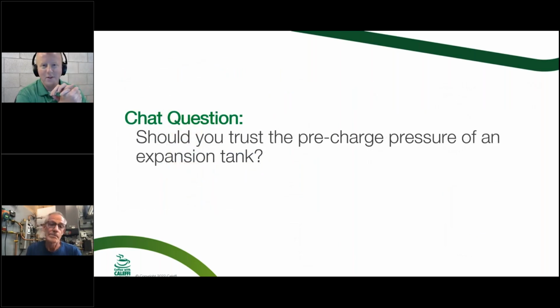Just a quick question for the questions pane there. Should you trust the pre-charge pressure of an expansion tank? We're seeing a resounding no from everybody that's jumping in there. Like Bob mentioned before, definitely check the expansion tank. Make sure you got a good gauge on there to get an accurate reading, especially a lower range on the gauge, so you get a little bit more definition. Don't check it with a 0 to 100 pound gauge, because you're not going to be able to get it as close as you need to.